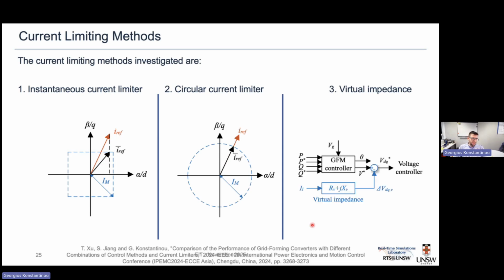So when we look at the current limiters directly, so the ones that allow us to directly limit the current, we have a few options here. Let's go through this quickly. We have the option of, as you can see, limiting the current directly. So whatever value we have, we instantaneously limit it to the nearest value. We can have a variation that allows us to proportionally limit it to P and Q values. So we can get on the D axis and Q axis, which allows us to control active and reactive power differently than the instantaneous current limiter. And we have the option I mentioned earlier of the virtual impedance that adds this delta VDQ here, which allows us to act on the voltage controller and limit the amount of current that we get out of the converter.